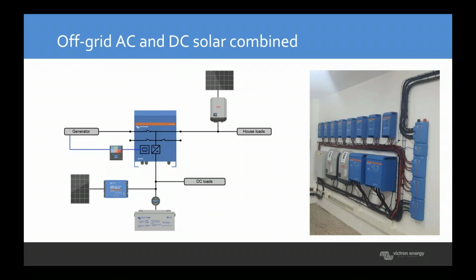in the form of, let's say, the salt batteries and the zinc bromide batteries, they can get to very, very low voltages. The Victron MPPT will still start up then. Then, once the battery voltage is up, the multi-plus will wake up, and the system will then start up again, and then you'll get the support of the Fronius AC PV. This is a much, much more reliable system. And if you are going to do off-grid work with AC PV, it's really strongly recommended to have a DC MPPT in the system as well for that blackstart capacity.